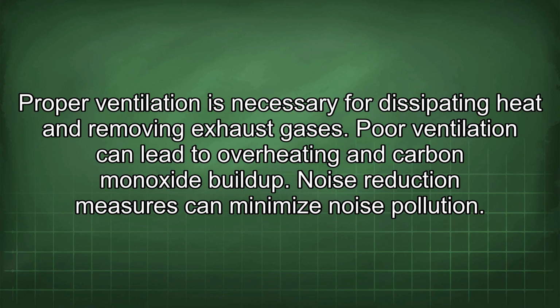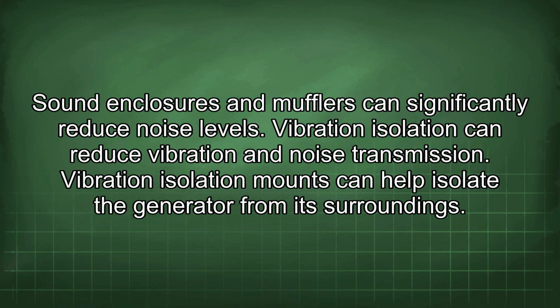Proper ventilation is necessary for dissipating heat and removing exhaust gases. Poor ventilation can lead to overheating and carbon monoxide buildup. Noise reduction measures can minimize noise pollution. Sound enclosures and mufflers can significantly reduce noise levels.